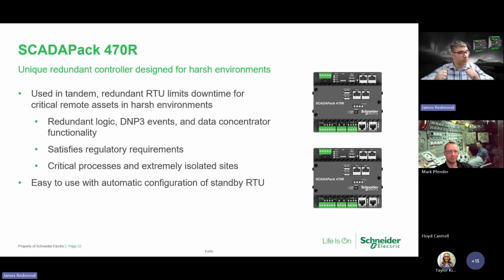So you take these two controllers, you put them in the same panel, or technically any place where they're connected to each other. One runs as the active controller, the other stays in sync in terms of the logic and the event database, as the standby controller.